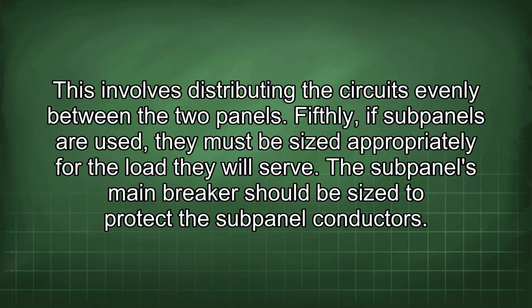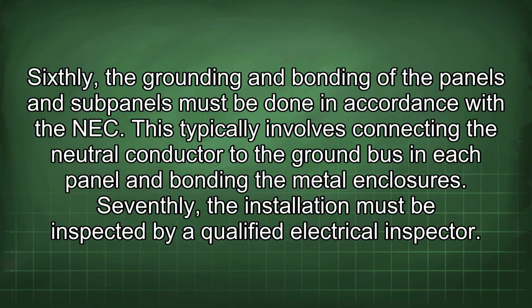Fifthly, if subpanels are used, they must be sized appropriately for the load they will serve. The subpanel's main breaker should be sized to protect the subpanel conductors. Sixthly, the grounding and bonding of the panels and subpanels must be done in accordance with the NEC. This typically involves connecting the neutral conductor to the ground bus in each panel and bonding the metal enclosures.